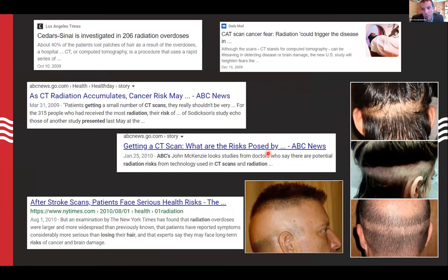What else does radiation do outside of image quality? If we use way too much radiation and do something grossly negligent with our CT scanner — like happened to a number of patients here — we can cause tissue effects. These patients all suffered skin reddening and hair loss because someone set up a perfusion protocol that was delivering diagnostic quality images for every time point, instead of vastly lower dose images for all those perfusion time points.